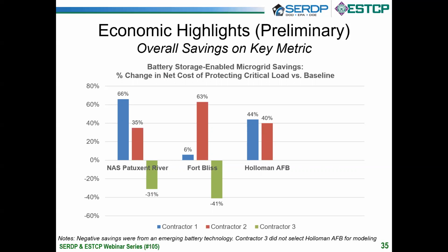So going back to the results for the investigators represented by the blue and the red bars, for Patuxent River, which is in Maryland and Delaware and then PJM electric market, you can see that inclusion of the battery in the microgrid improved economics by 66 and 35% for the 2 contractors and reduced it by 31% for the third one. On the plus side, those percentage savings translate into about $500,000 of savings per year at the 66% level, and about $275,000 of savings annually at the 35% level. And that's after including all the costs of buying, integrating, and operating the microgrid and the battery. So you get all the reliability benefits while creating savings.